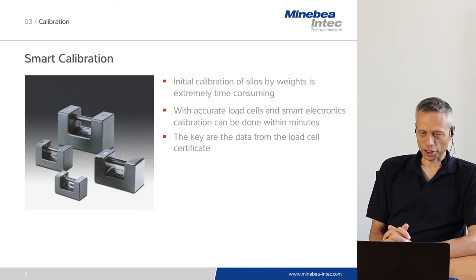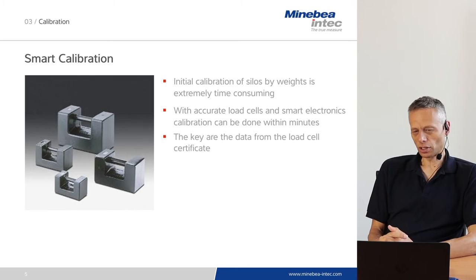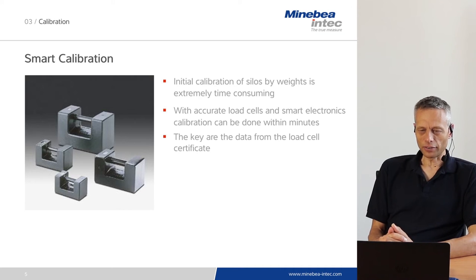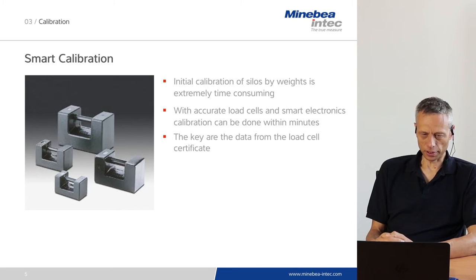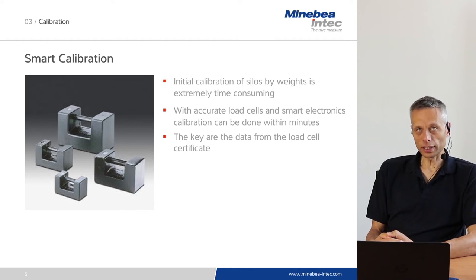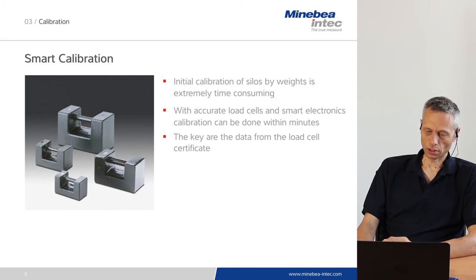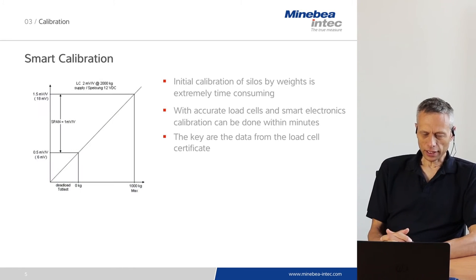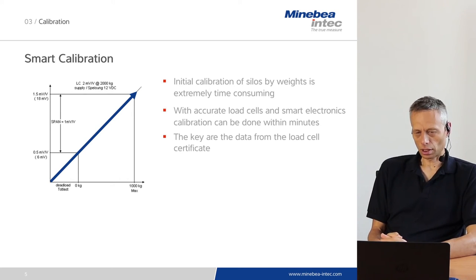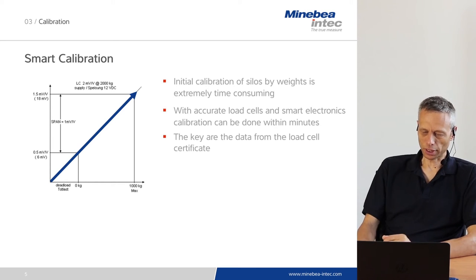Since initial calibration of silos by weight is extremely time consuming, there is a need for an alternative method. We assume that the load cells which are installed are very accurate and that the mechanical installation of the whole silo has been done properly. Given these conditions, we can perform a smart calibration which is based on software and the calibration data of the load cells. Smart calibration means calculating an expected full scale deflection value based on load cell data found on the certificates.